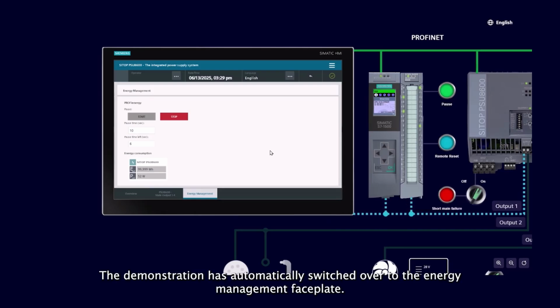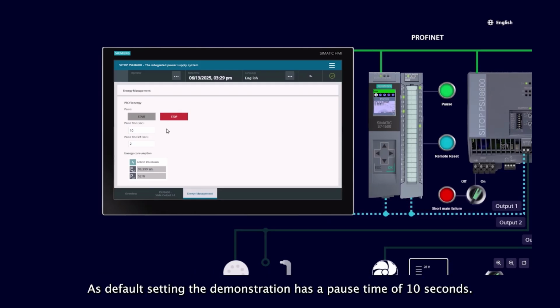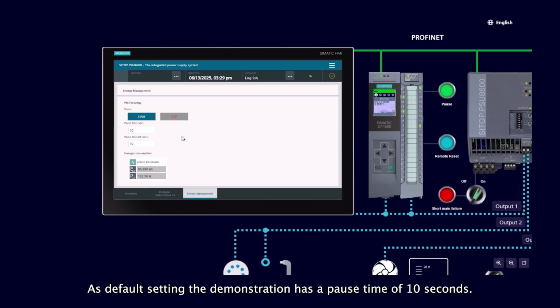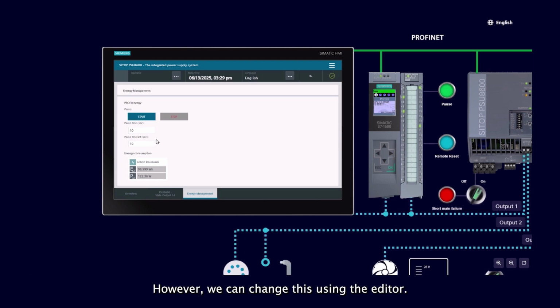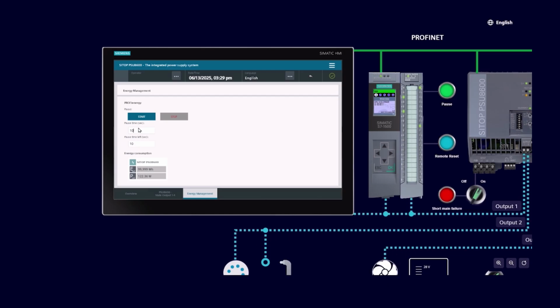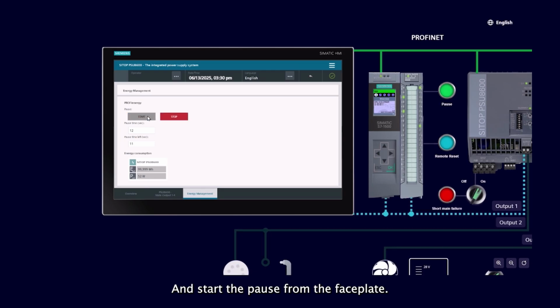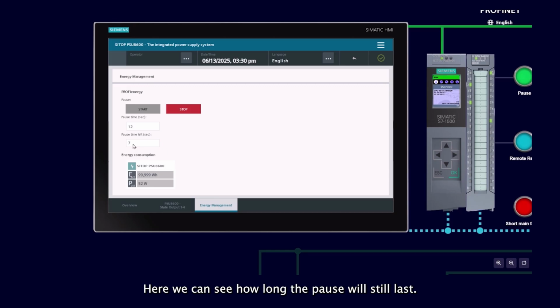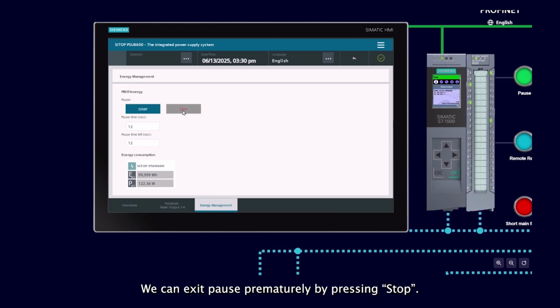The demonstration has automatically switched over to the energy management faceplate. As default setting, the demonstration has a pause time of 10 seconds. However, we can change this using the editor and start the pause from the faceplate. Here we can see how long the pause will still last. We can exit the pause prematurely by pressing stop.